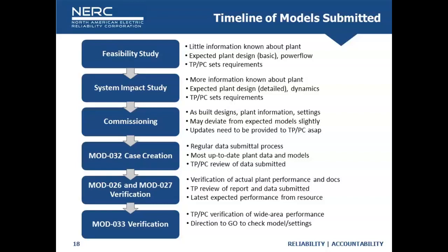Mod 26 and Mod 27 are what Bob kind of mentioned, and I'll talk a little bit about those. Those are the verification standards of actual plant performance, looking at either a stage test or a disturbance and comparing the model to that to see if it matches. Again, the TP reviews the test report that's provided and the data submitted, and they can flag technical concerns if they have any. That should be the latest expected performance from the resource based on the latest test that was performed. I'm going to talk in detail about Mod 26 in particular here in a second.